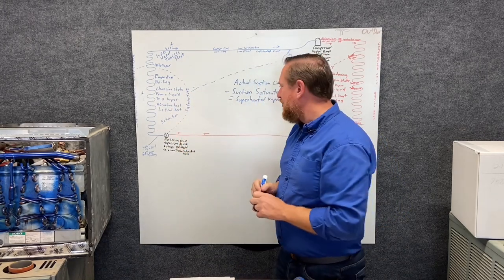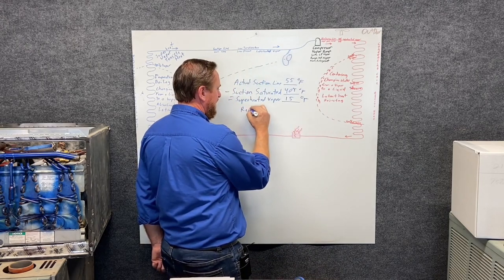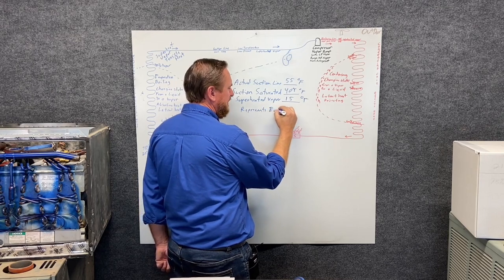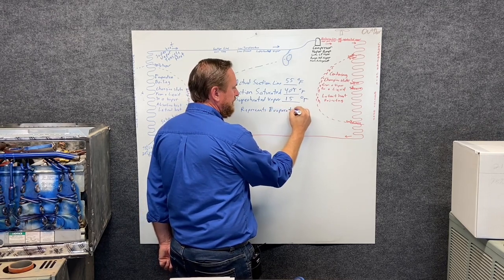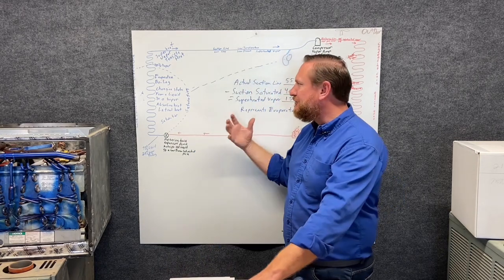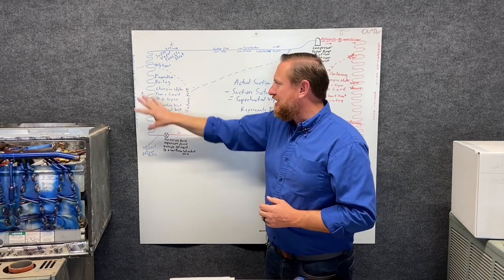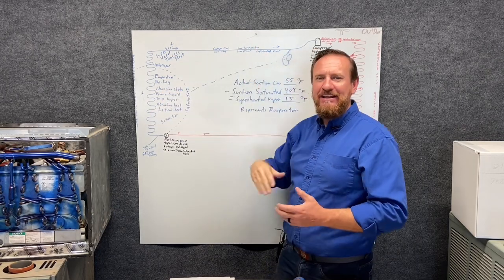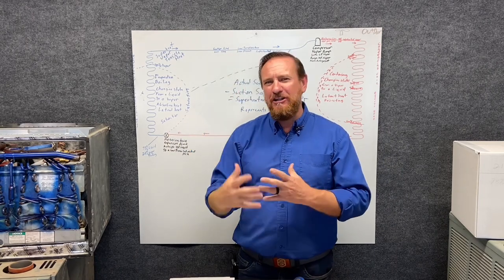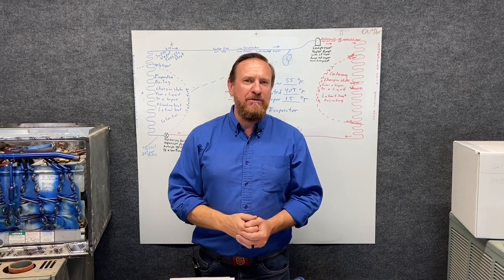So make those notes. Superheat, low pressure, its measure represents the evaporator. Represents evaporator inside. Very, very, very important. So it's the amount of sensible heat added to a vapor above saturation. Saturation's here. We've added superheat above that. So that's the most important part of superheat.